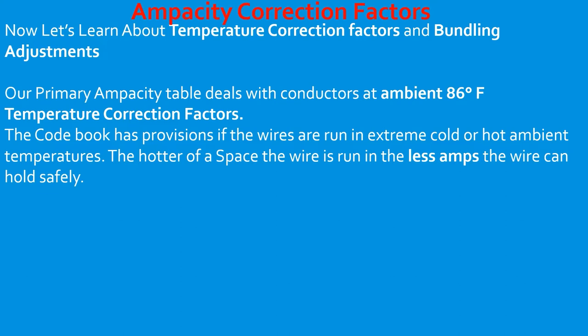The codebook has made provisions for wires run in extreme cold or hot ambient temperatures. The hotter the space the wire is run in, the less amps the wire can hold safely. The colder the weather, the more amps the wire can hold safely. If the temperature around the wire is super hot, it's going to be less able to dissipate the heat, and the heat may degrade the wire and insulation itself, reducing safe ampacity.